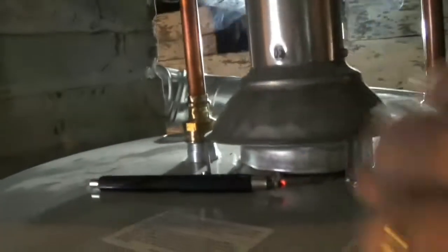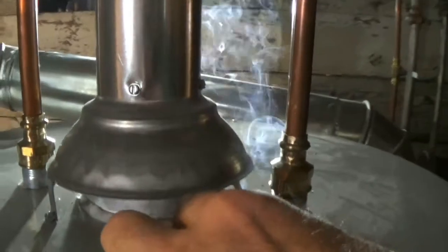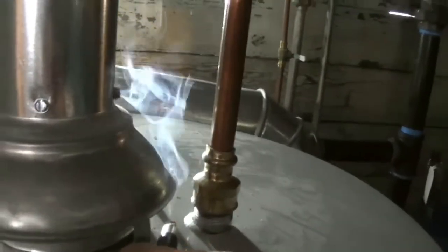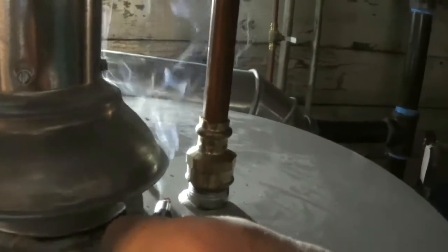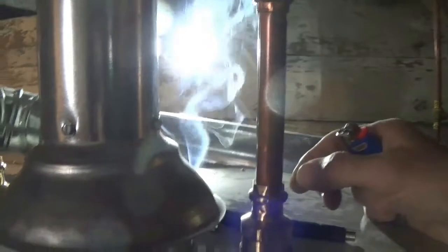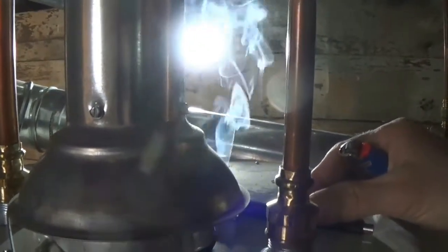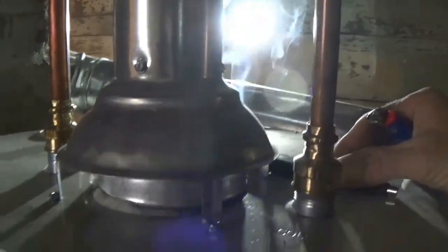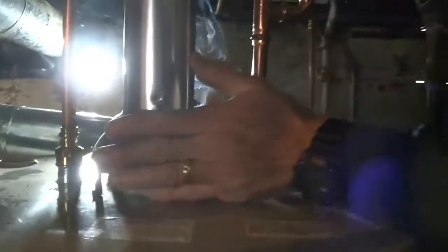so you can see it's kind of almost half and half here, but it really wants to be all going in to pass. And it's just not really. Are you saying almost doesn't count? It doesn't count. Almost passing isn't passing. We really want to see that smoke getting sucked in, like sideways, into that draft opening. And we don't want to feel any hot exhaust coming out here.